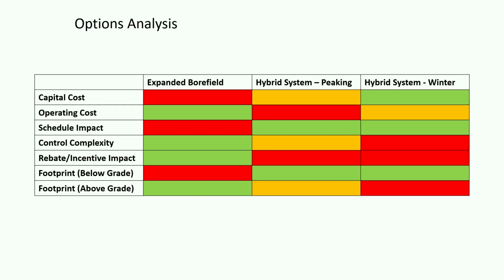Factoring into capital cost, schedule impact. If you have to drill more boreholes further out, that takes time. We don't have limitless time. Time is money. So this is another scenario where you may want to use one of these 2 types of hybrid systems to compensate. Controls complexity. It's not complicated at all to run a bore field with a couple more boreholes or further apart. However, once you start adding these separate hybrid systems in, depending on the type of BMS system the customer has, you somehow need to integrate that, and that's something that you need to work with in the design phase, and that factors into your decision making.